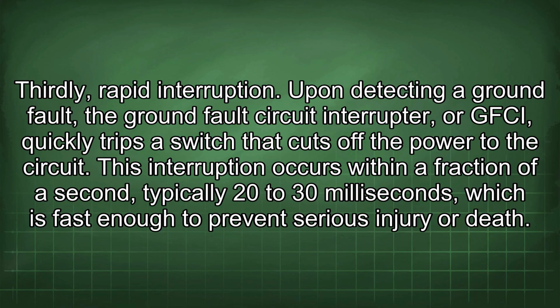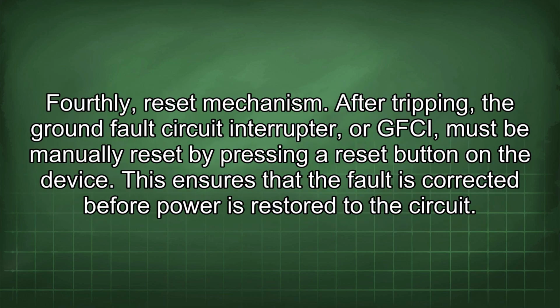Thirdly, rapid interruption. Upon detecting a ground fault, the GFCI quickly trips a switch that cuts off the power to the circuit. This interruption occurs within a fraction of a second, typically 20 to 30 milliseconds, which is fast enough to prevent serious injury or death. Fourthly, reset mechanism. After tripping, the GFCI must be manually reset by pressing a reset button on the device. This ensures that the fault is corrected before power is restored to the circuit.